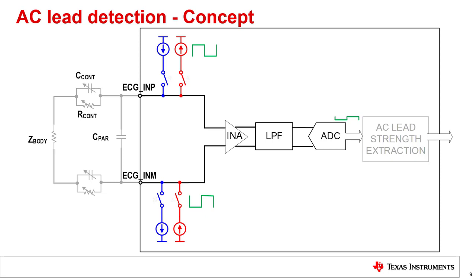The capacitance C-parallel, shown in the figure, represents the equivalent differential capacitance between the ECG input pins when the leads are off. Such a capacitance could be a combination of the input capacitance of the ECG pins, the PCB trace capacitance, as well as the capacitance resulting from the electrode metal plates. The parallel R-contact and C-contact represent a model for the AC contact impedance, and Z-body is a model of the impedance of the body between the two electrodes. For simplicity, we assume Z-body to be negligibly small compared to the electrode contact impedance.